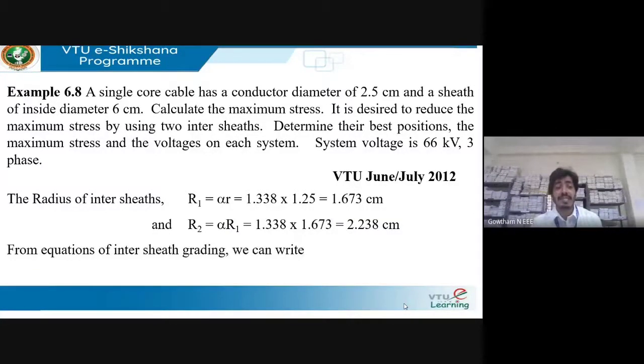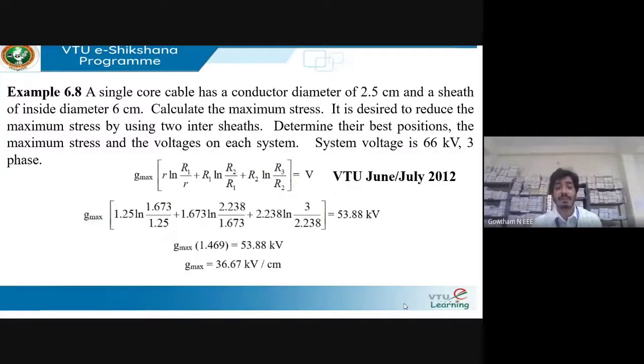Using the equations of inter-sheath grading, V = V1 + V2 + V3. On substituting the values, the maximum stress Gmax = 36.67 kV/cm.